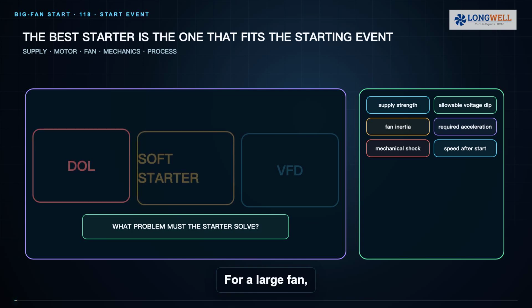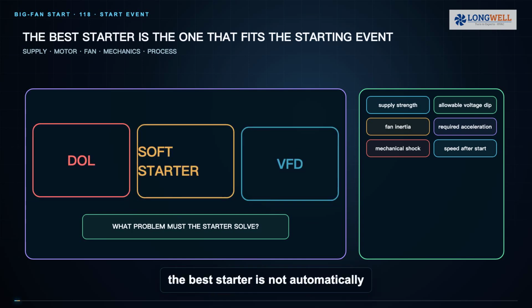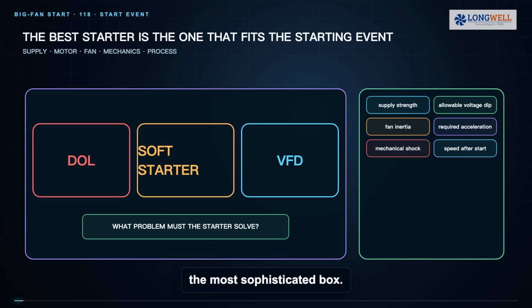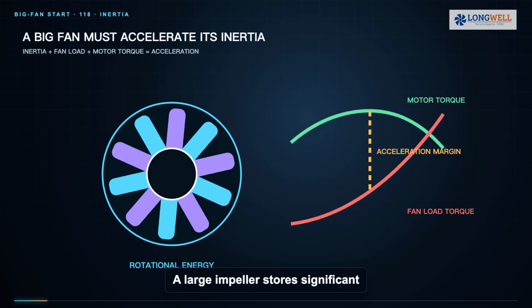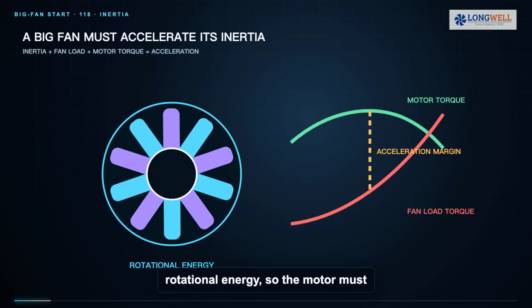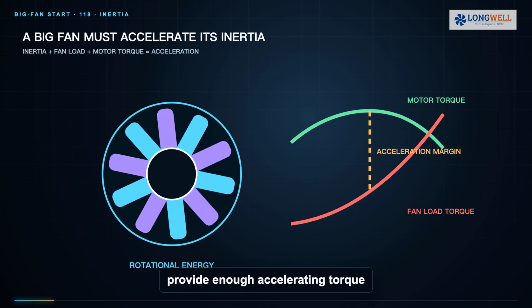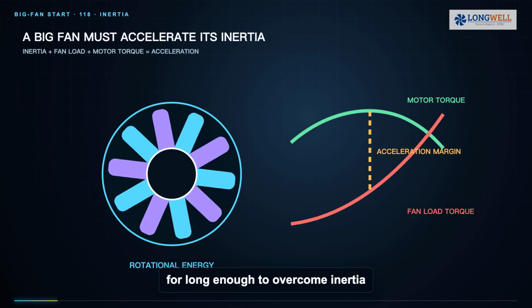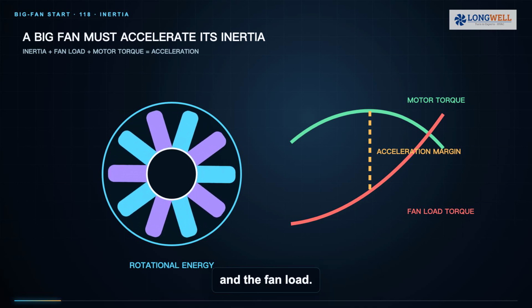For a large fan, the best starter is not automatically the most sophisticated box. The decision begins with the starting event: how much current the supply can tolerate, how quickly the fan must accelerate, how much mechanical shock is acceptable, and whether the process needs speed control after the motor reaches operating speed. A large impeller stores significant rotational energy, so the motor must provide enough accelerating torque for long enough to overcome inertia and the fan load.